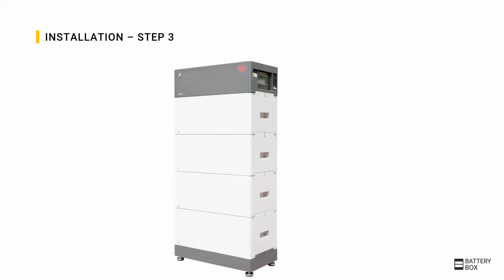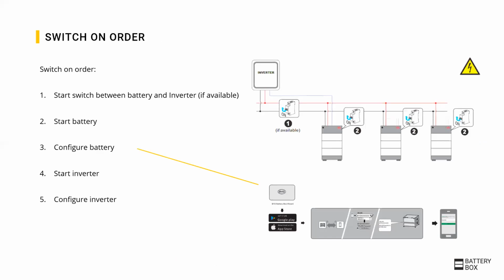The next step is commissioning. For this, the battery needs to be activated by the system switch on the right side of the BCU. Here, the correct switch-on order is important. If there is a switch between the inverter and the battery, that needs to be turned on first. After this, the battery should be started and configured.